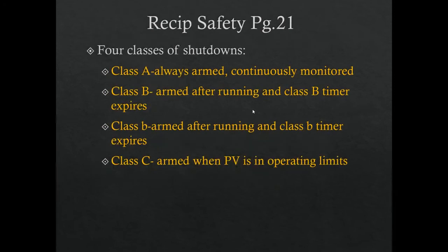Okay, reciprocating safety, talking about shutdowns and overall supervisory type control for a reciprocating compressor. So there's four classes of shutdowns that we associate with reciprocating compressors, and they're classed. So just like we have hazardous location classifications, we have safety shutdown classifications for compressors, so reciprocating compressors in particular.